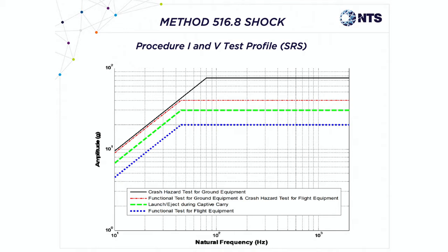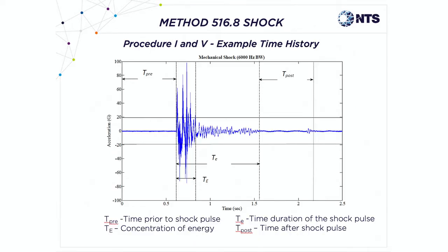There's a big TE and there's a little TE, which is the duration of the test. When you read the document, it will say there's not enough time. If you have to make the curve all the way down to 5 hertz, there's not enough time in the allotted window inside MIL-STD-810G to hit the whole curve. So if you've done some research and you don't have any resonances in the low frequency, we can miss that response spectrum, the shock response spectrum, the SRS, on the low frequencies.